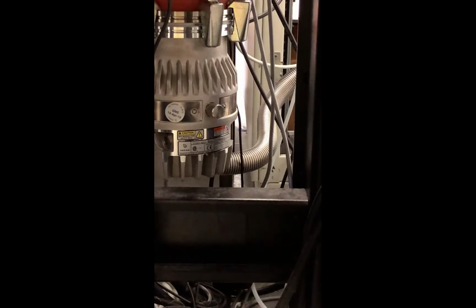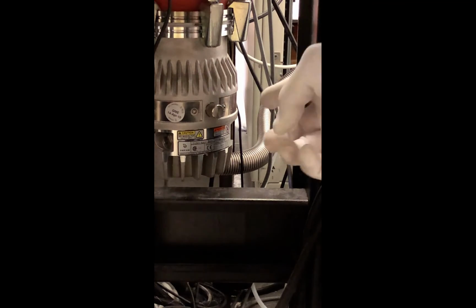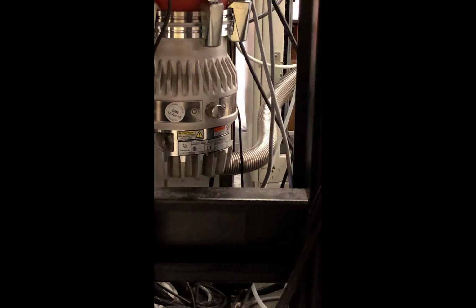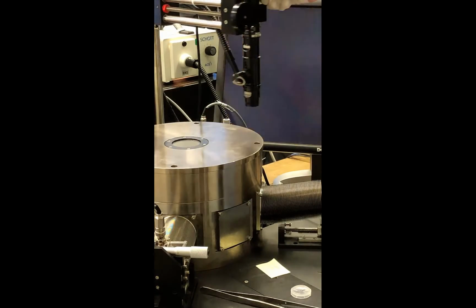When the sample chamber pumps down correctly, you'll see the pressure start to fall. You'll also be able to hear that the roughing pump grows quieter the longer it pumps. If you notice that it's not pumping down, you might want to check the turbo pump vent valve to make sure there's no leak. Once the pressure is in the range of 10 to the minus 1 torr, you're ready to continue.